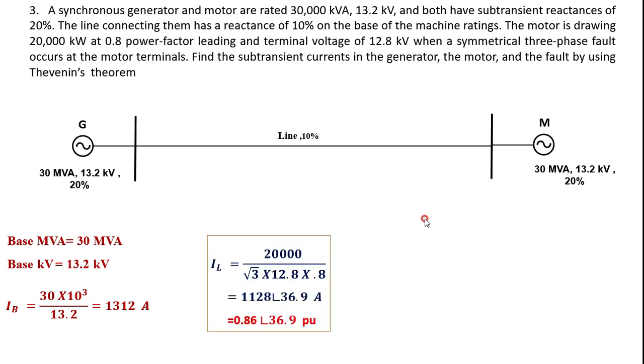One more parameter to calculate is the load current. The load is 20,000 kW at 0.8 power factor leading at 12.8 kV. The load current IL equals total power divided by root-3 times line voltage times power factor, giving 1128 amperes at an angle of +36.9° (positive because it is leading power factor). Converting to per unit by dividing by the base current of 1312, the load current is 0.86∠+36.9° per unit.